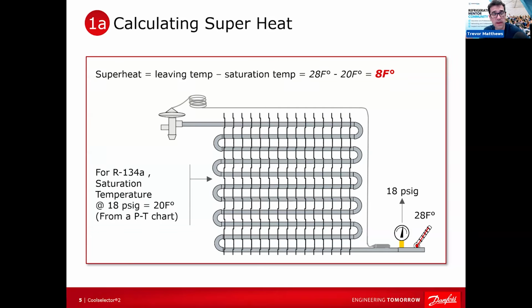People go in and look, oh man, I got bubbles in the sight glass, or there's something wrong with the system. I got to add gas or something to it. And they didn't even check superheat, or they check superheat and the superheat's off. And it's like, I got to adjust the TX valve, and we'll dive into that. That's not what you do. Don't touch the TX valve, man, please. Don't touch it. Unless somebody was monkeying with it before you. You don't want to be that person, right? Because if it's not the problem and you monkey with it, now you've got two variables, right? One you created yourself and one you haven't figured out yet. And two variables, as you remember from high school, is a lot harder to solve than one.